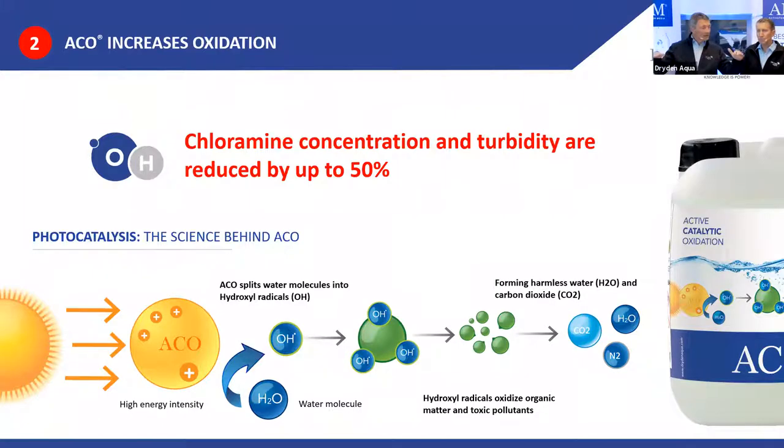You can even see this if you have an automatic pool cover. Open your pool on a sunny day with ACO in the water and watch your redox potential — without dosing any chlorine, your ORP will increase by 50 to 100 millivolts within 15 to 45 minutes, depending on hydraulics. If you control your chlorine by ORP, your free chlorine demand will go down because the ACO is providing supplemental disinfection.